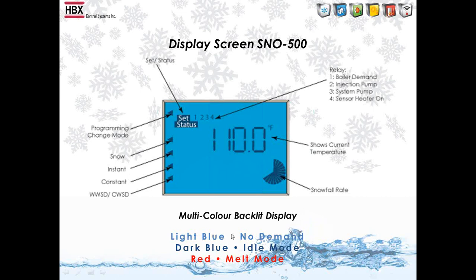So these are things that we will ask you if you phone in. We will ask you, what numbers does it say on the screen as far as up in the top left-hand corner, because we want to know if the boiler demand's on or if the heater's on, because that's very important. So the backlit display, obviously light blue, there's no demand. It's kind of a whitish light blue. Dark blue is when we're in idle mode, and red is when we're in melt mode. So you can see right away when you're looking at the control what mode it's in. So we will ask you if you phone in what color the screen is.